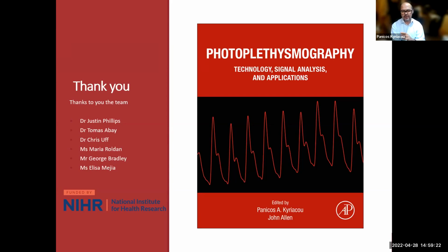But for those that are now spending enough time in this space, they appreciate the value of having this multiple wavelength technology that can scan through absorbers and through wavelengths from the visible, from the blue, if you're going after bilirubin, from the blue, green, red, NIR, moving into the other bands that you are entering: lactate, glucose, urea, of course, water bands. And if you can multiplex those wavelengths within a technology, it will employ computational techniques. It will enable you to discriminate dynamically a lot of absorbers within the blood.